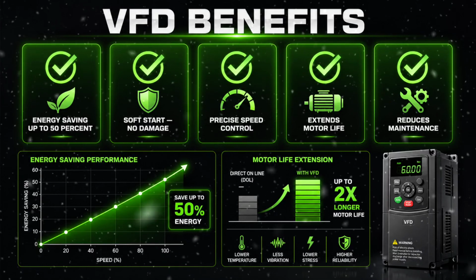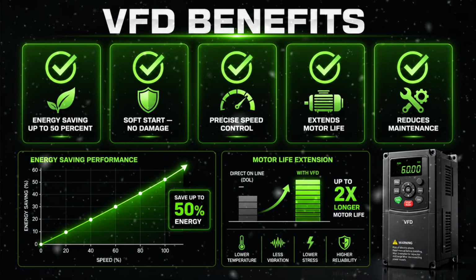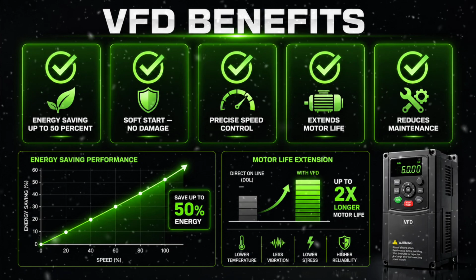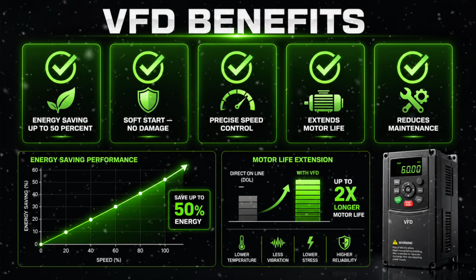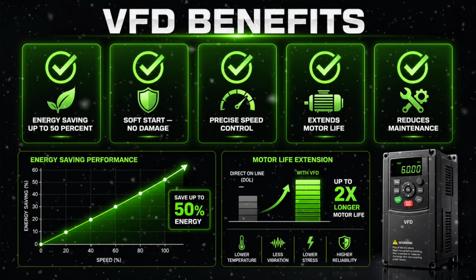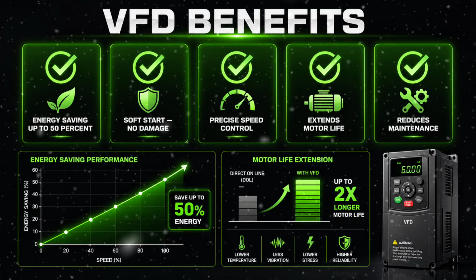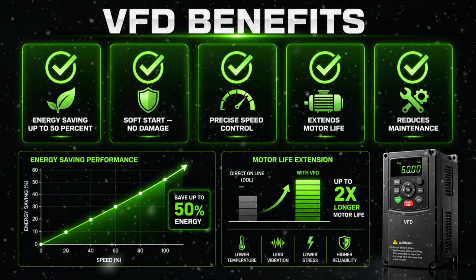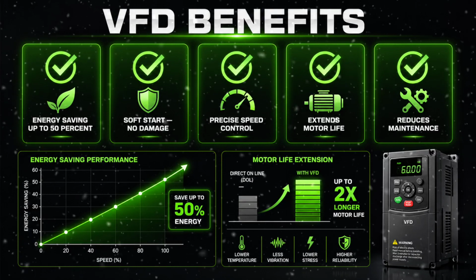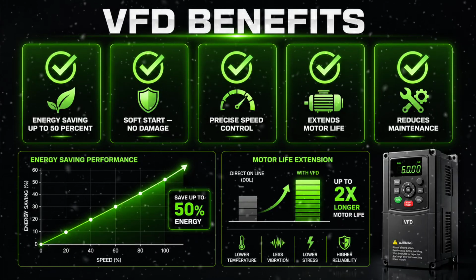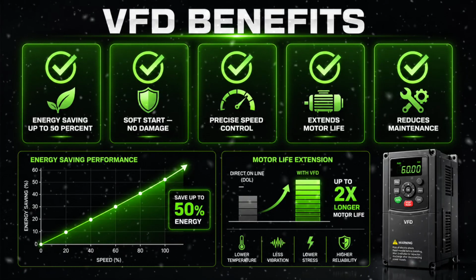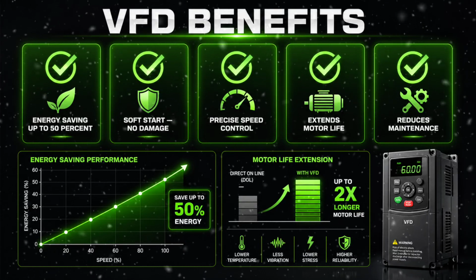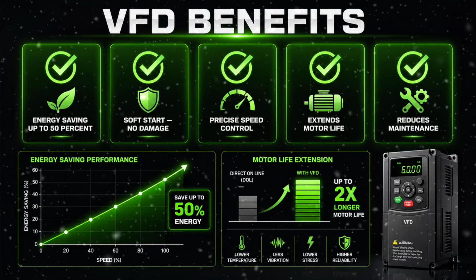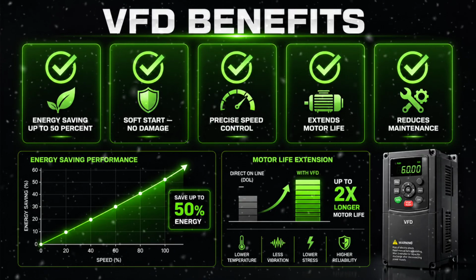Now let us talk about the real benefits of using a VFD. Benefit 1. Energy savings. A pump running at 80% speed uses only 51% of the energy compared to full speed. This is because power varies with the cube of speed. This saves massive electricity costs every year.